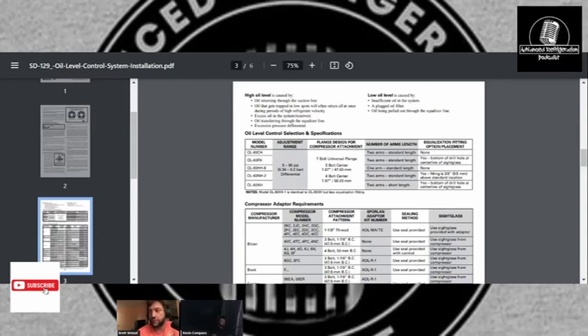Let me bring this up real quick, since we're talking about the Sporlan one of these. You can see up there it says adjustment range 5 to 90 psi. That's basically the differential between the suction and the oil pressure. Most mechanical oil level regulating controls have a max of a 90-pound differential. So you have to watch. Some Henry ones only have a differential max of 30. So if something were to fail, let's just say your OCV would fail and it would just keep the pressure really high, like at rack pressure, you've just now grenaded that oil level control. No bueno. No good at all. Those ones fail more, to be honest with you. It's not every single model. There's some that do and some that don't.